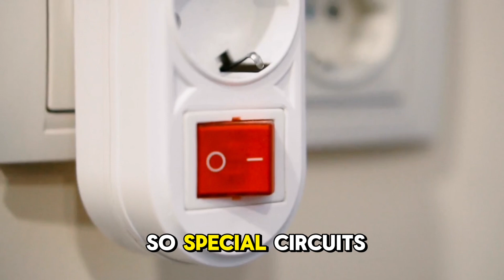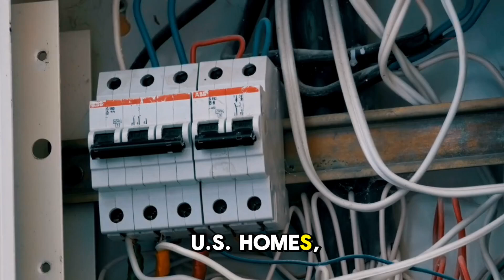Dual voltage in the US. It's worth noting that the US does use 220 to 240 volts for certain high-power appliances, such as electric ovens, dryers, and air conditioning units. These appliances typically require more power than what 110 to 120V can provide efficiently, so special circuits are installed in homes for these devices. In most U.S. homes, the electrical system delivers both 110 to 120 volts for standard appliances and 220 to 240 volts for high-powered devices.